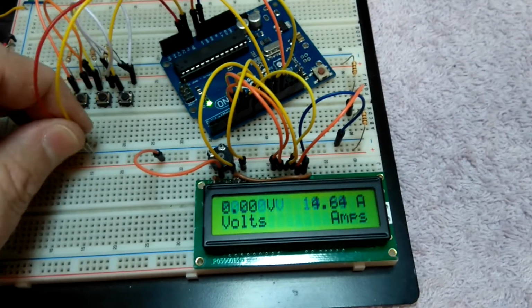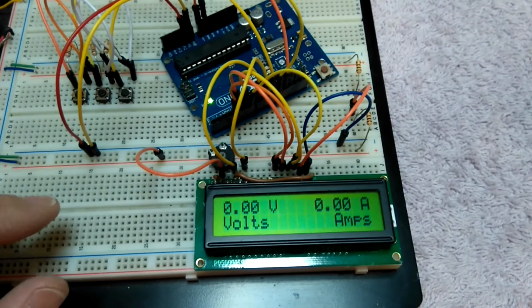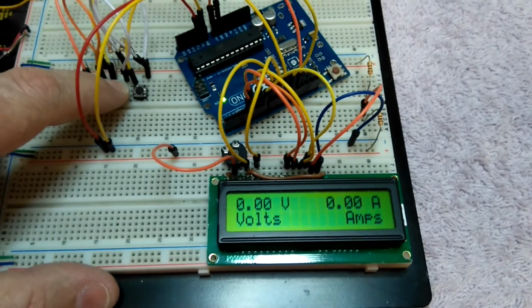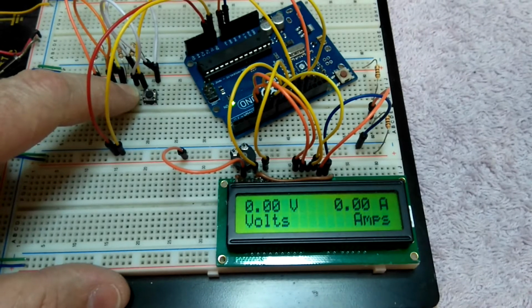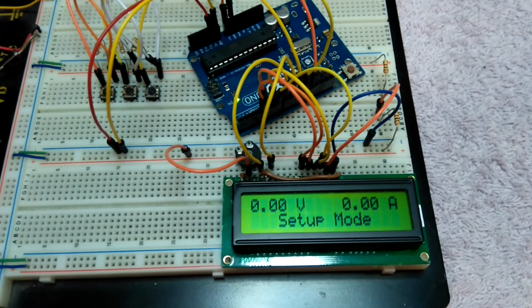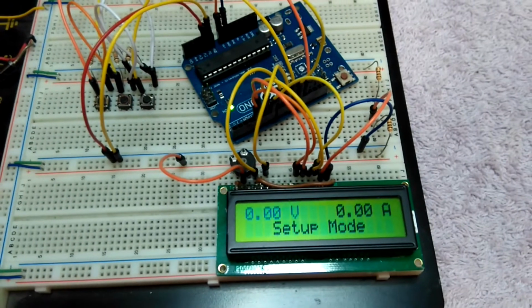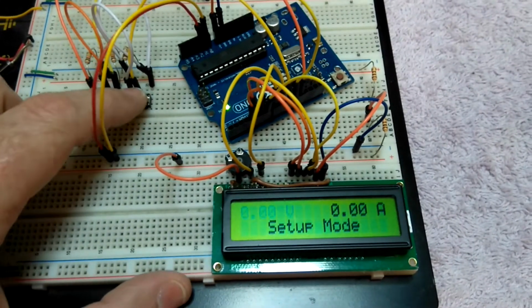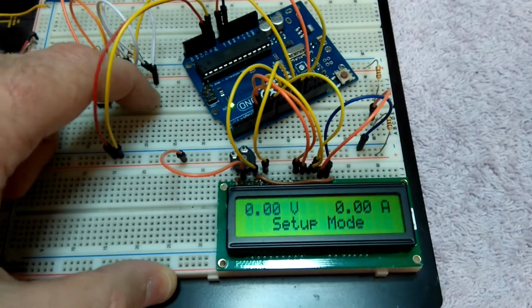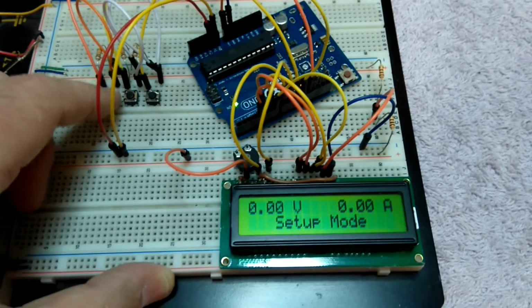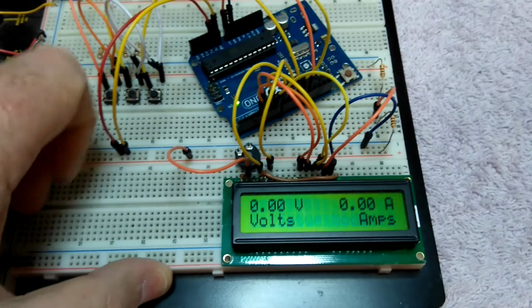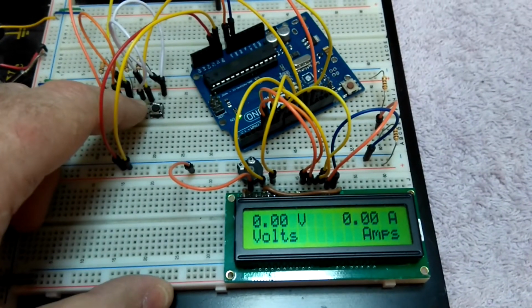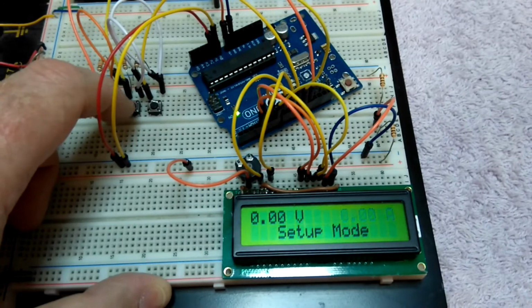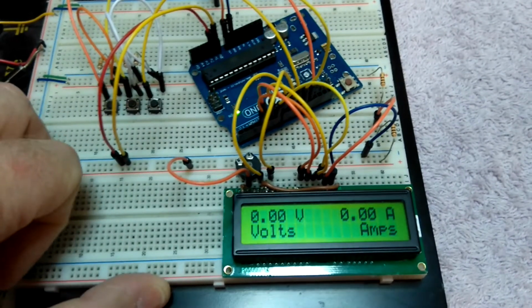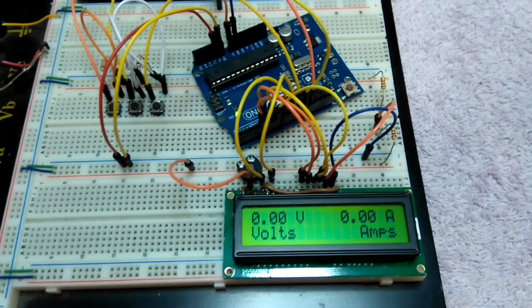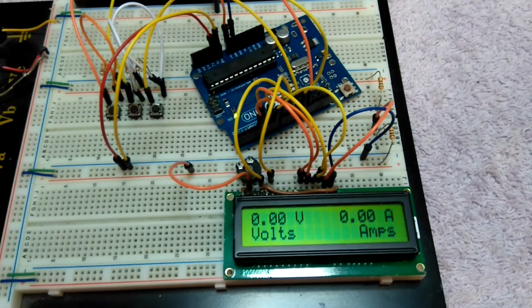Is that if you quite simply need to do an alignment on this, you basically push and hold the middle button. There's no pots to trim or anything. It'll go into setup mode, and with a known voltage input over there, you can then do up and down alignment. Basically, like so. Whatever the case may be. And then change to your amps. Do the same thing and then save it out, and it will save it up into the AVR's storage permanently.